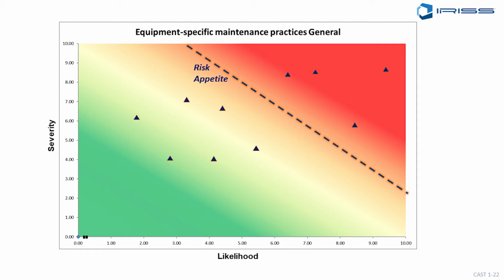Appetite for risk. And the stuff in the upper right-hand corner, right, that may be 5% of the assets in your facility. And you might say, you know what, on that stuff, I am so uncomfortable with what happens when it fails and how much it's going to cost us when it fails that I might want to actually think about online monitoring, temperature monitoring, partial discharge monitoring, power quality monitoring, online everything. Give me data 24/7 on that asset so now I know exactly what's going on.